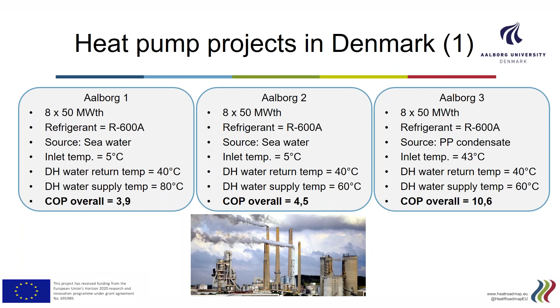What we can observe from these numbers is that the lower the supply temperature the heat pumps have to deliver, the higher the COP, and the higher the heat source temperature, the higher the COP. In some cases, heat pumps can have a COP of 10 if they're using high temperature heat sources and also supplying low temperature district heating systems.